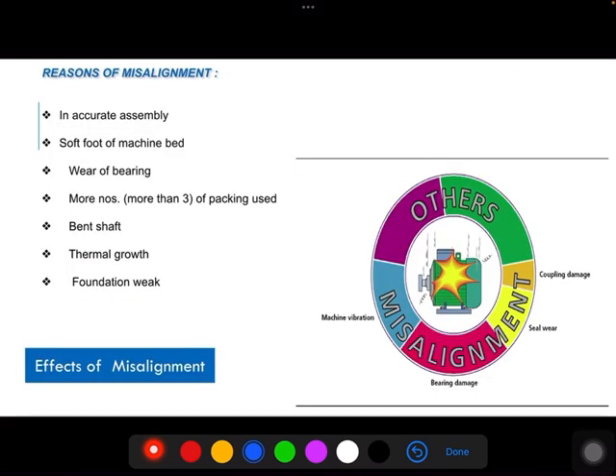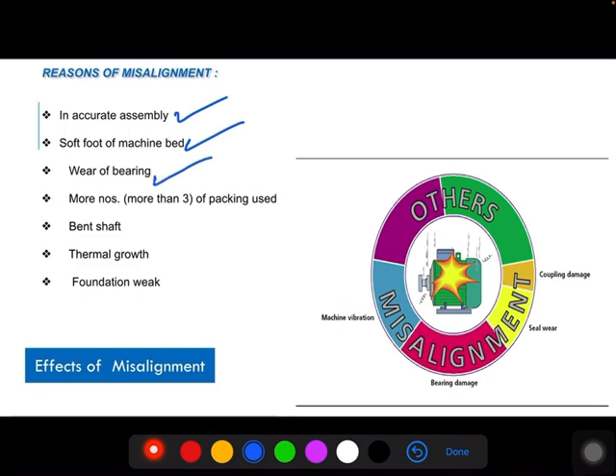What are the reasons for misalignment? There are many reasons. If the assembly is not proper in a motor, pump, or any machine, it results in misalignment. In the case of a soft foot in the motor base, pump base, or fan base, it also results in misalignment. During operation, wear and tear of the bearings due to lubrication issues results in misalignment of the shafts. If you use more than three shims during alignment at the bottom of the base, it also results in misalignment. A bent shaft also results in misalignment.